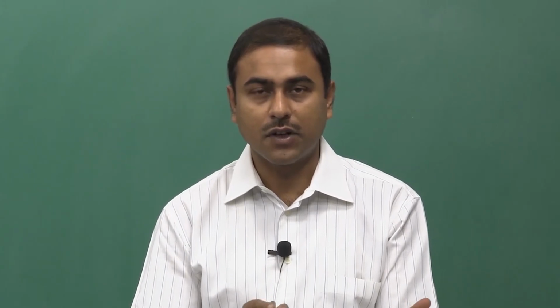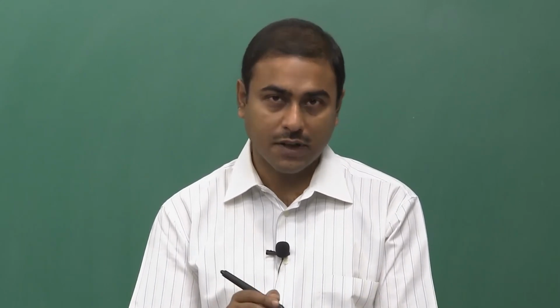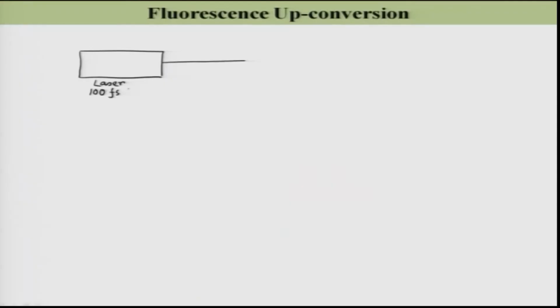This is my laser, which can generate a very short light pulse, because my aim is to have an instrument response function in the order of 100 or 200 or 300 femtosecond. So obviously, if you use a light pulse of 200 picosecond, then the instrument response function cannot be 100 or 200 femtosecond. So you have to use at least a 100 femtosecond light source. So let me take this as a 100 femtosecond pulse it can generate.